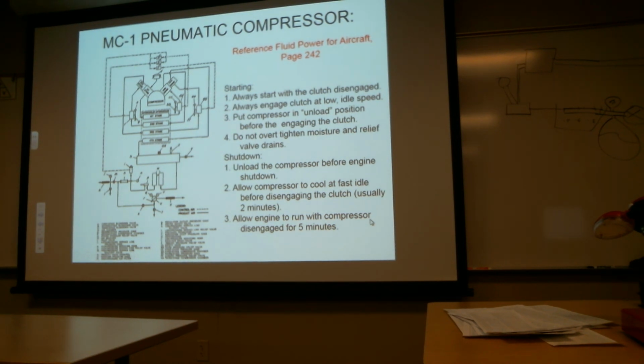There's a reason for this: the lubricating oil inside the compressor can coke and form a hardened compound. Not necessarily sludge, but a hardened material that's very abrasive. So you're trying to prevent the coking of oil that leads to contamination of the oil and possibly damage to the compressor from its abrasive nature.